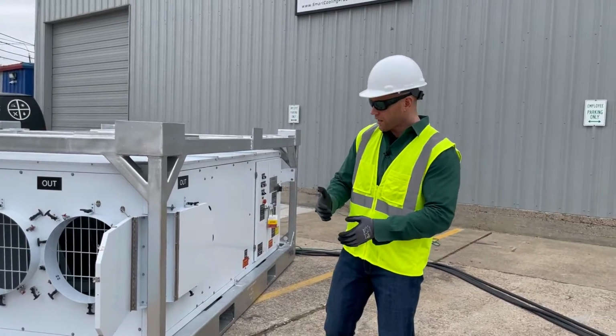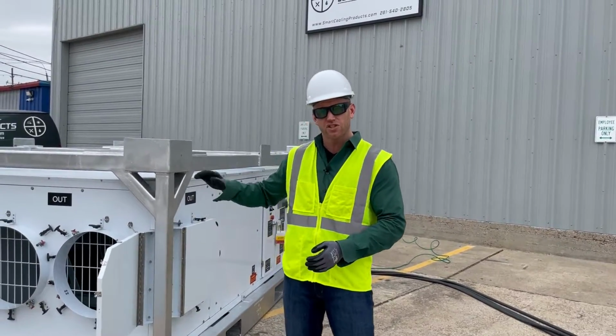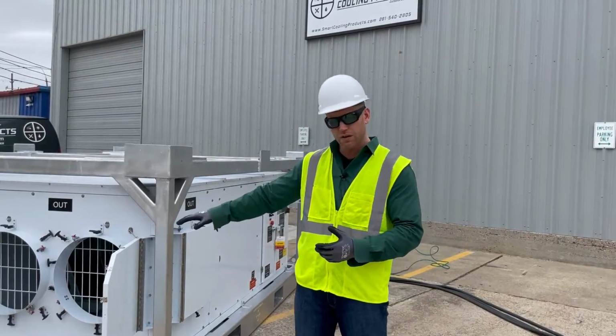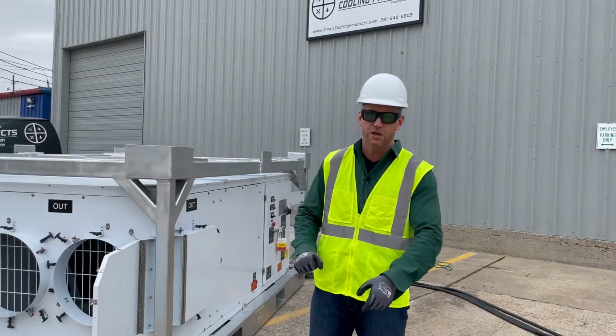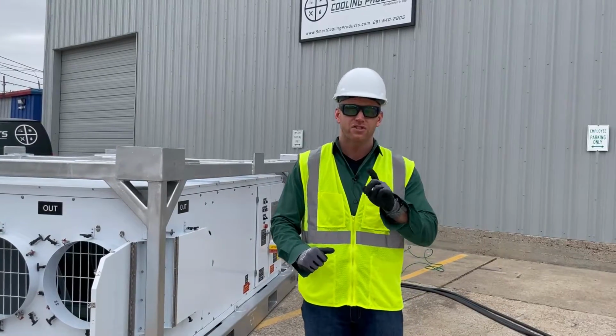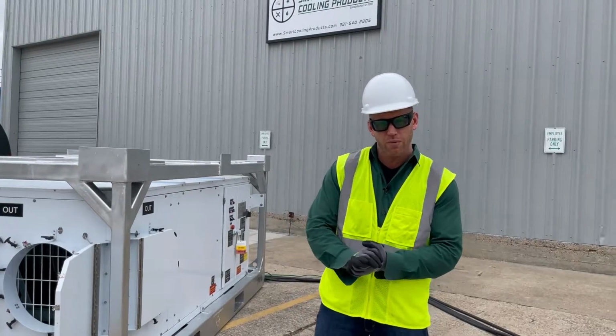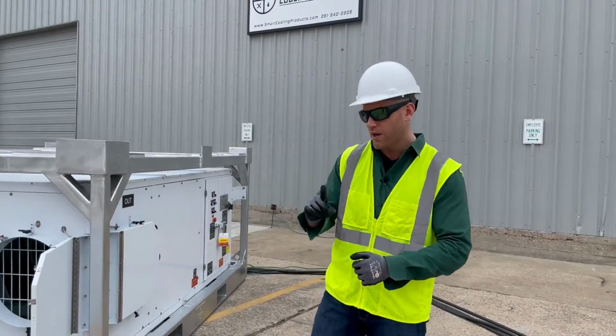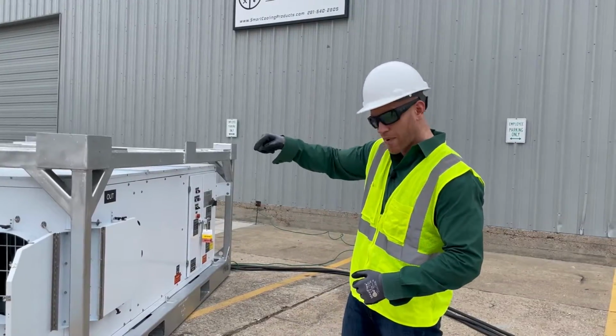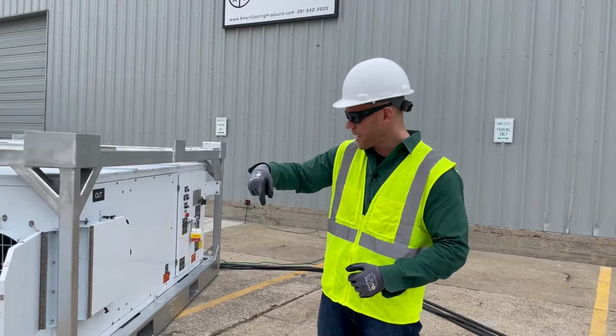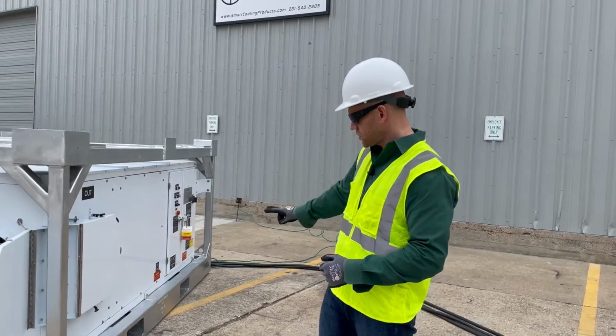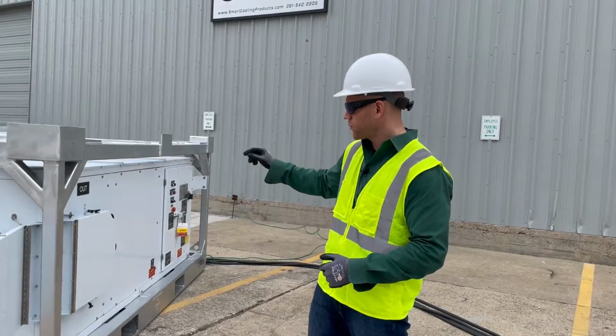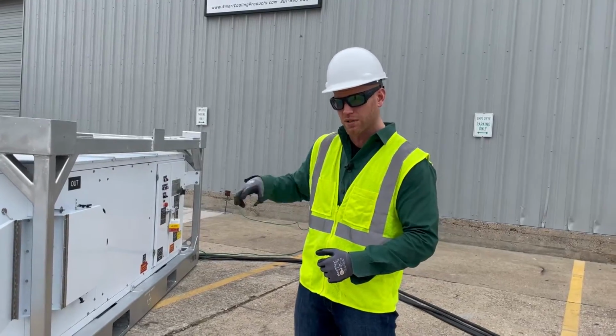So that's it. Our air handler has been successfully started up, and we've ramped it up to the airflow and static pressure the job requires. Now let me go through those 5 startup steps one more time just so that we have it together. Step number 1, when you receive the unit, inspect it, do a full walk around of the package. Make sure that it's lifted correctly and set in place either with the fork pockets or the overhead lifting points.